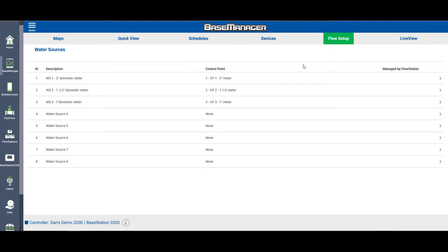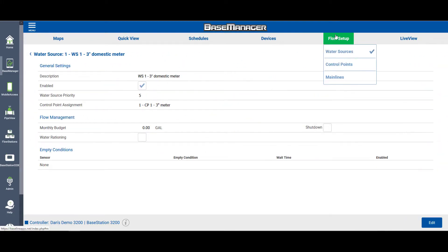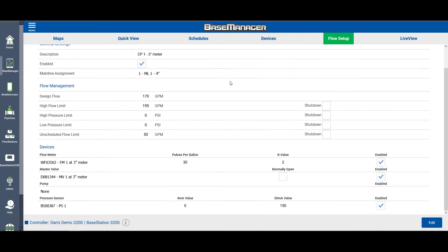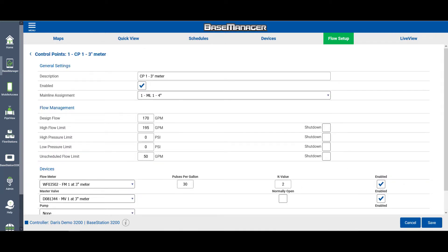I'm going to start by assuming that you've set up your master valve and control point correctly in the flow tab in App Manager or Base Manager, or at the controller. If you've done that correctly, all of this will make sense. To answer your question very specifically, Jeff: you can't program the master valve alone. What we're going to do is create a program for a dummy zone, and when that dummy zone opens — which won't run any water — the master valve will open and allow the mainline to pressurize.